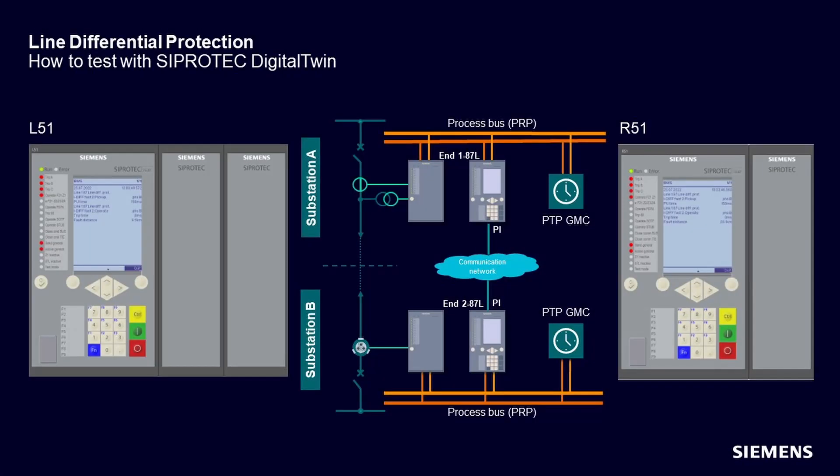In this example, we have a process bus application with the analog values being received as sampled measured values. However, as we are doing our process bus implementation in SIPROTEC Digital Twin stepwise, and the subscription of the SMV in the client devices has not been released yet, we are going to inject the protection devices directly.